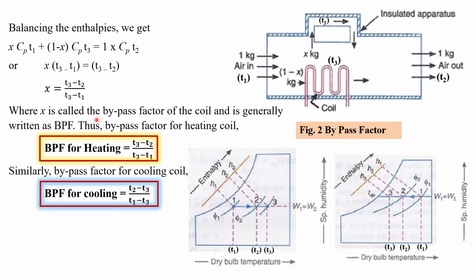So here the term x is called the bypass factor or the cooling factor of the coil and is generally written as BPF. So for the case of heating, it is going to be (T3 minus T2) divided by (T3 minus T1). It's quite clear by looking at the psychrometric chart plotted for the sensible heating case and for the sensible cooling case. In the case of sensible heating, the heating coil is maintained at the highest temperature. Air is made to flow over this heating coil initially at temperature T1. So it flows over the heating coil, but the temperature of the whole chunk of the air is not changed up to T3. Rather, it exits from the system at temperature T2.